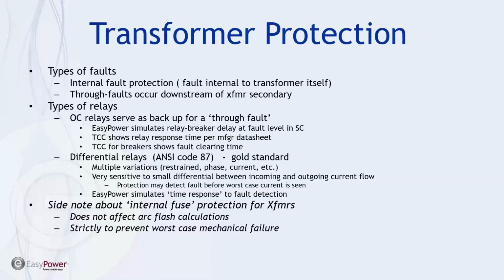So we reviewed most of this on Monday, but basically we're looking for through faults. If the transformer has an internal fault, there's nothing we can do about it. We have to decommission it. And so there are several types of relays that can be used to determine a through fault. And we're going to try to go through a couple of these.